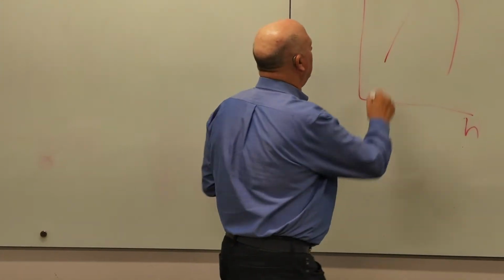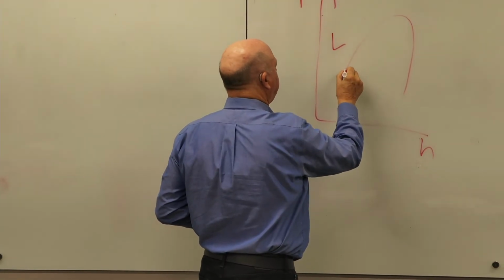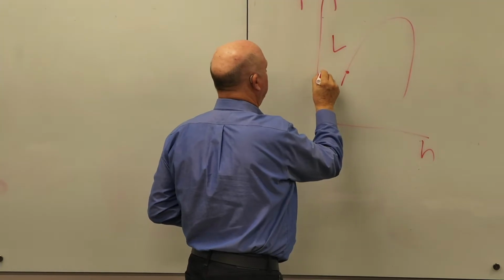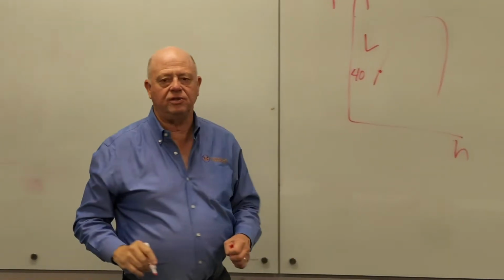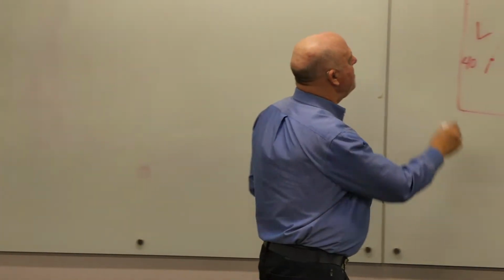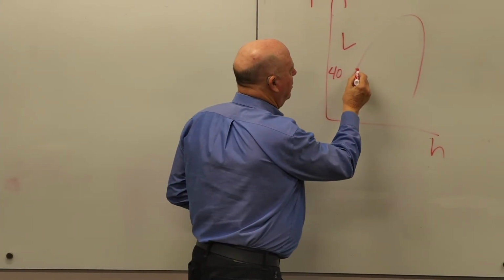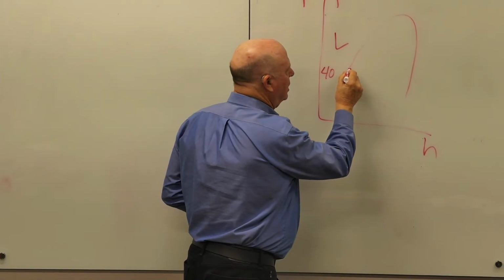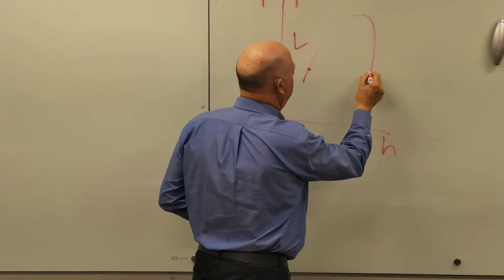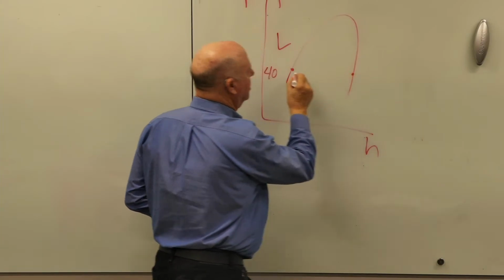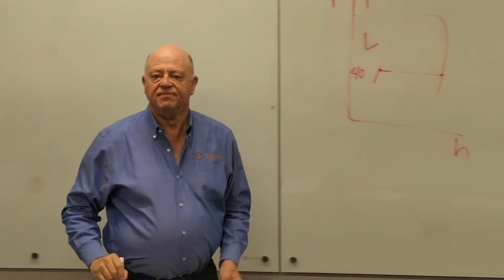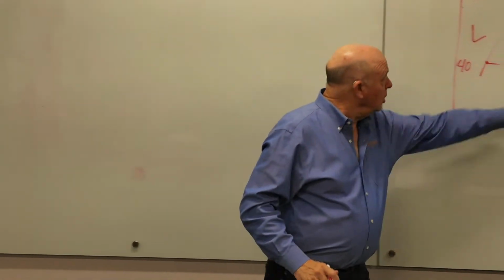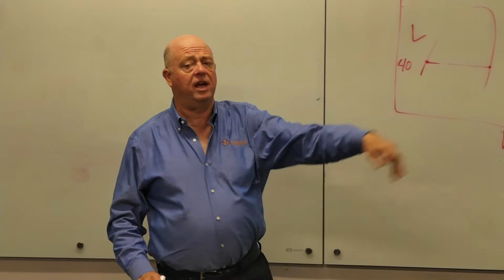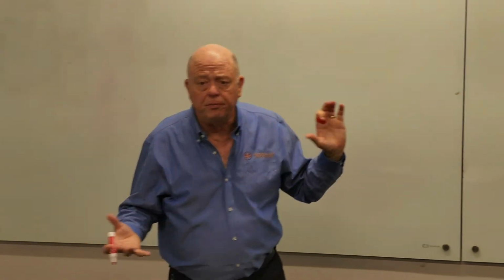And we start over here on the liquid side. If this is 40 degrees, and I keep going to that because that's a good cooling coil temperature, kind of a nominal number. At 40 degrees and all liquid, it's here. At 40 degrees and all gas, it's here, right, with a straight line. And it's linear across here. If you were halfway across that line, it'd be half liquid and half gas.